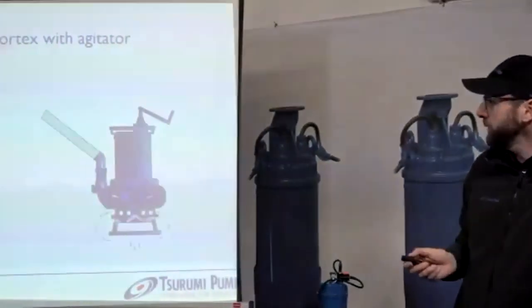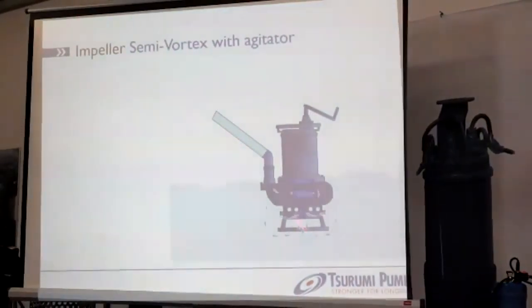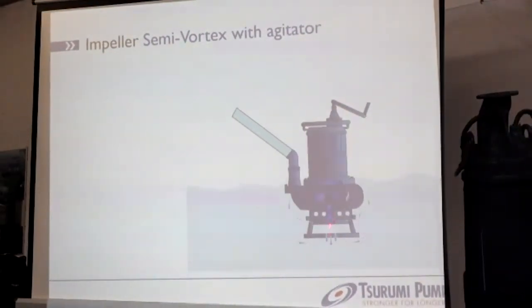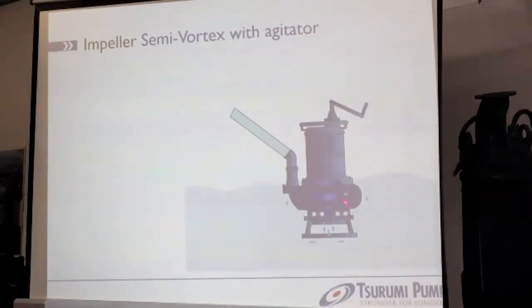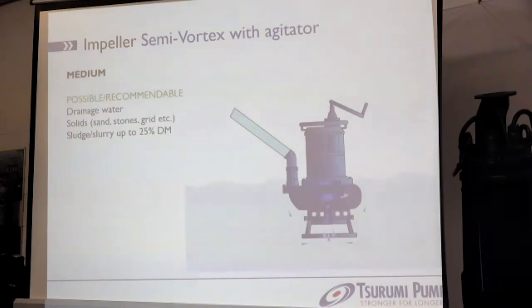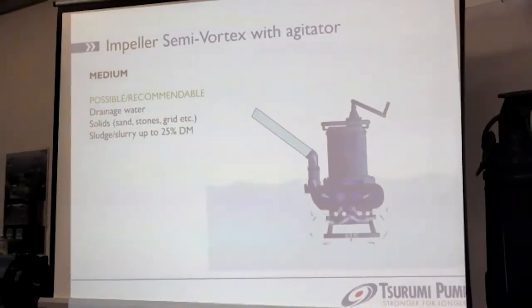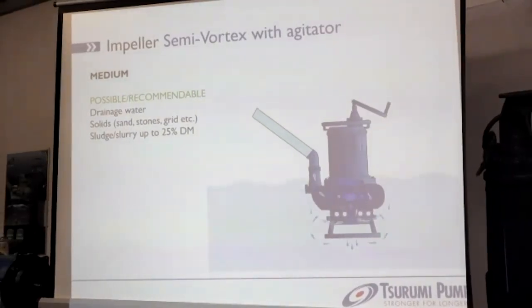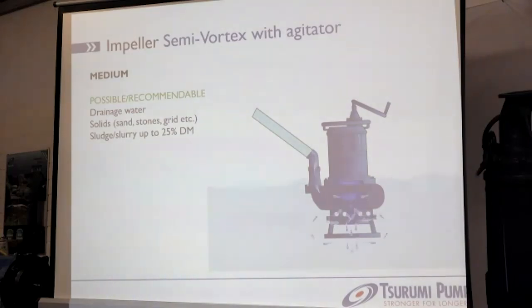The agitator hat rotates, creating a downward streaming that crowds up the medium, and then the pump sucks it in and transports it away as a mixture. Recommended mediums are drainage water, solids like sand, stones, gravel, and slurry up to 25% dry matter — but remember 25% is the maximum for the biggest agitator pump, the GPM, not the smaller ones. Please consult us to check values for smaller pumps.